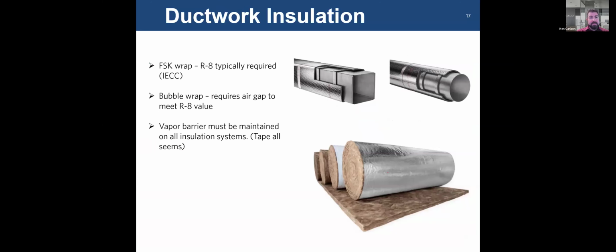A couple things to know about ductwork, right? Typically, ductwork insulation needs to have an R8 value. That's required by IECC. It's also referenced in ACCA. You typically use FSK. It's foil scrim kraft. It's what they call the fiberglass insulation that you see here on the bottom. That has an R8 value. A lot of people these days are using bubble wrap. All right, bubble wrap doesn't actually have an R8 value, depending on whether you're using the thin or the double. Even double bubble, as the industry often calls it, a thicker bubble wrap, even that doesn't have an R8 value, to my understanding. I think it's an R6.